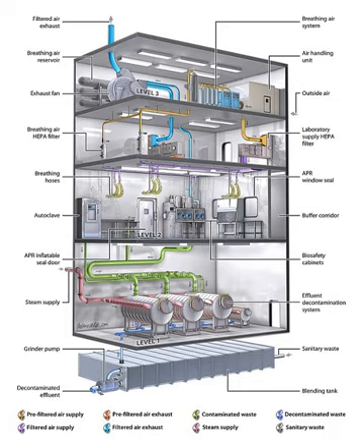At biosafety level 2, all precautions used at biosafety level 1 are followed, and some additional precautions are taken. BSL-2 differs from BSL-1 in that laboratory personnel have specific training in handling pathogenic agents and are directed by scientists with advanced training. Access to the laboratory is limited when work is being conducted. Extreme precautions are taken with contaminated sharp items. Certain procedures in which infectious aerosols or splashes may be created are conducted in biological safety cabinets or other physical containment equipment.